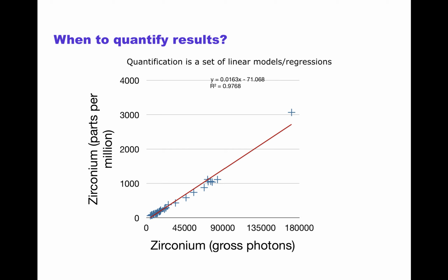To think about the validity issue, let's think of a hypothetical point, one that is much further out there. You see the little red plus sign far to the right and to the upper right. In this case, we have something that falls outside our calibration curve. Can we continue our line to meet that point? The answer is no, we cannot. While we would get an answer, and it may be close to the right answer, what we lose is the ability to express uncertainty. Our uncertainty past our maximum data point approaches 100% pretty quickly.